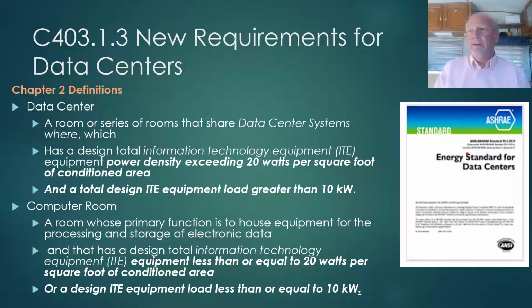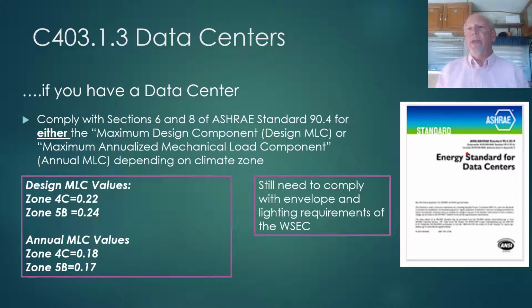So let's talk about 90.4. If you have a data center, per C403.1.3, the HVAC serving that data center shall comply with Section 6 and 8 of ASHRAE Standard 90.4. Now, Section 6 specifically is around the efficiency of the heating and cooling system, or essentially the cooling system serving that data center, and Section 8 deals with the power system, including UPSs serving the data center.